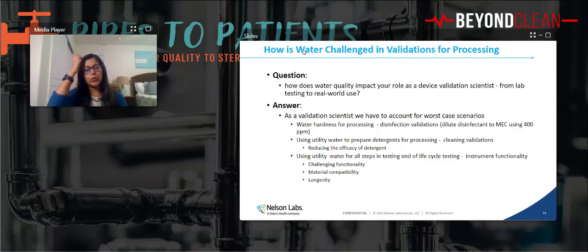And for utility water, we use it to prepare detergents. Yes, detergent water hardness changes season to season—Utah sees four different seasons, so we account for that. We're challenging the detergent for the cleaning process, making it ineffective for cleanability, but doing the validation to the worst case to show that if the right waters were not used, it still can be reprocessed safely.